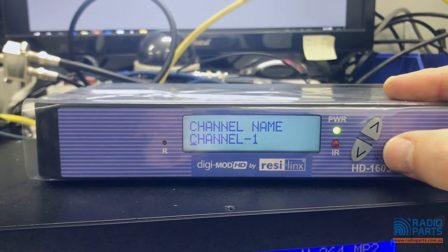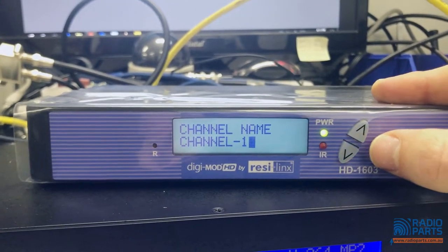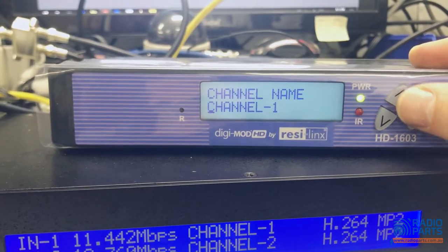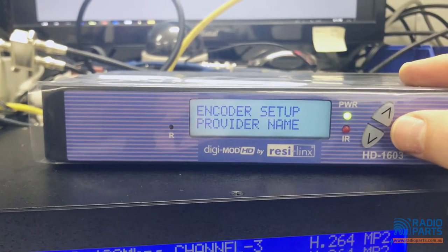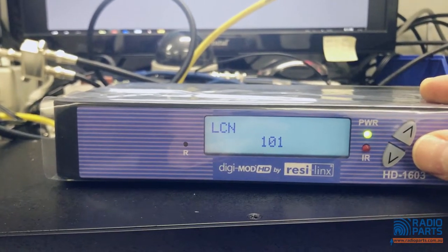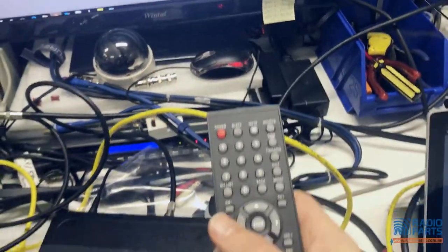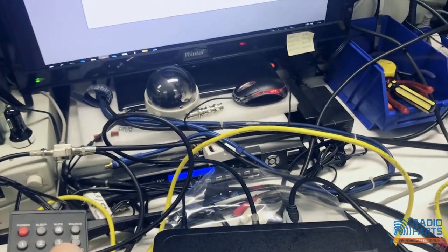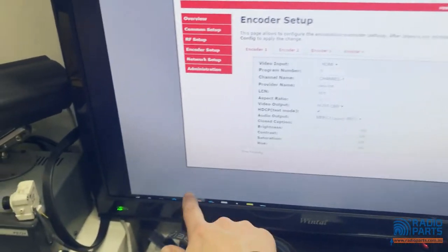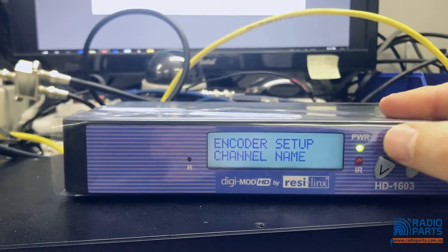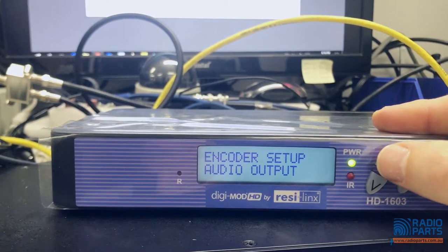The program number and channel names are really useful. So if you did set this up as Foxtel, you'd punch in the name Foxtel, and when you tune it in on the TV screen it'll appear as the name Foxtel. LCN is also a useful one — if we're using multiple channels, this is LCN 101. You can tell that by getting the remote control and typing in 1-0-1 Enter, and that will come up as the modulator channel. To set up, go through channel name, provider name, and LCN.